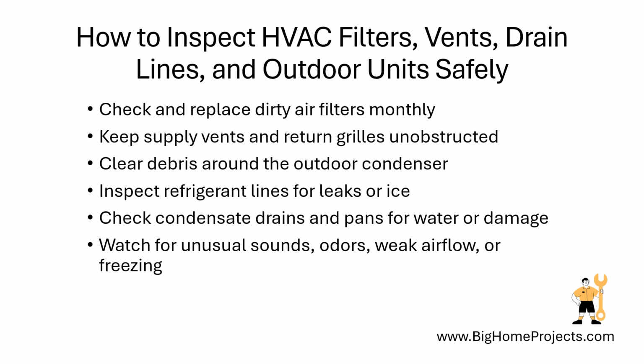Inspect the condensate drain line and drain pan for standing water, algae, rust, or cracks, because a clogged drain can cause water damage and may shut off the system. Listen for new banging, grinding, buzzing, or squealing sounds, and notice unusual smells or weak airflow.